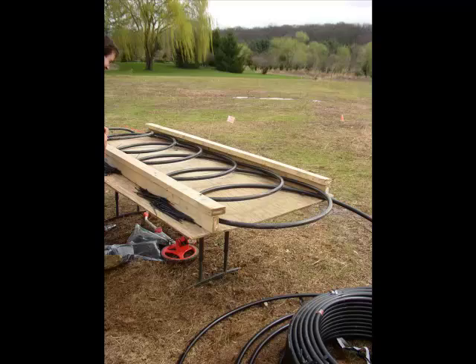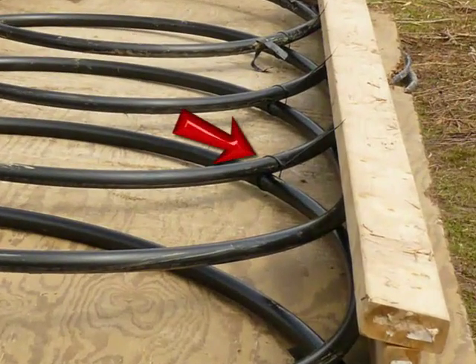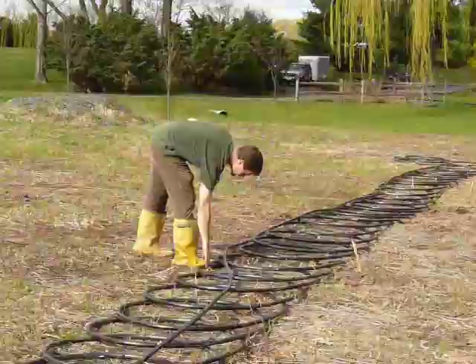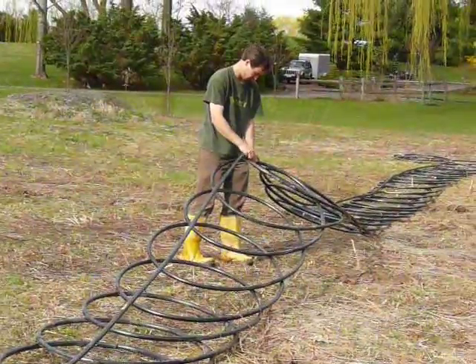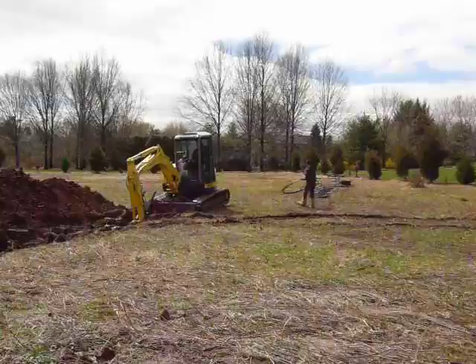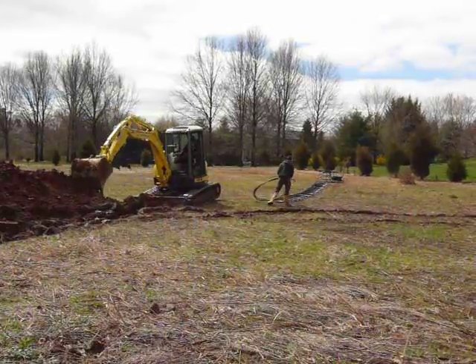Meanwhile, there needs to be some prep work done on these pipes. Underground loops are created from each coil using a rig to standardize the coil size. You'll see the loops flattening out on the table, and they're locked into place with cable ties. Each 800-foot coil is stretched out in this uniform way to create a 100-foot loop, and the return pipe is locked into place too. These two processes — the digging and the prep work — occur at the same time. It's certainly a race.